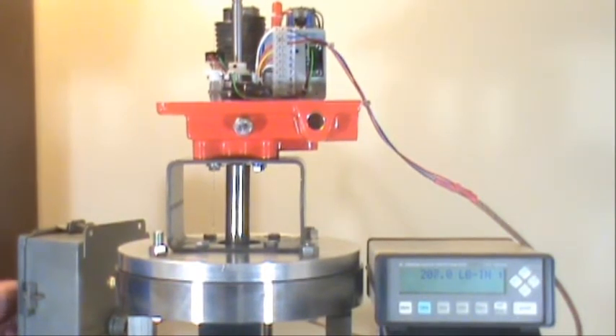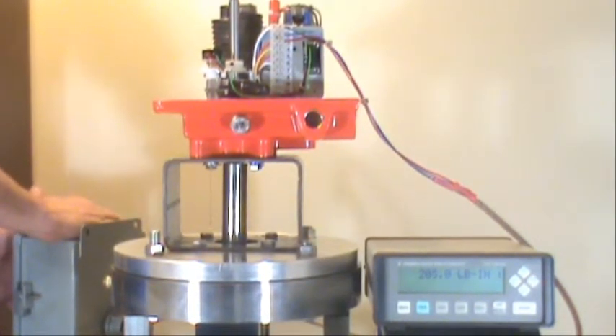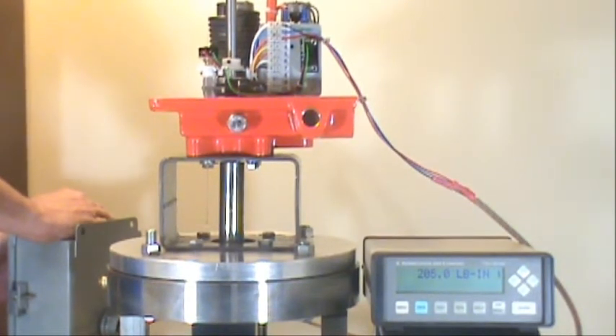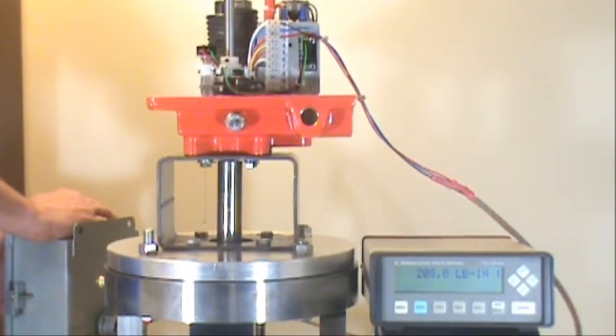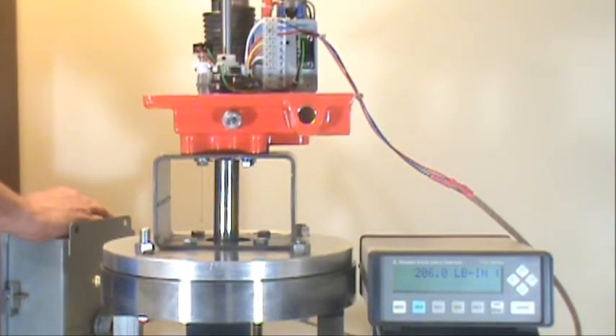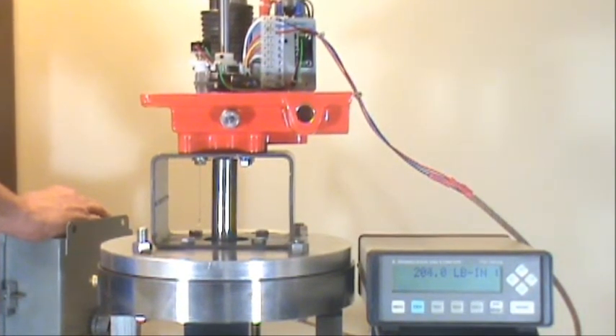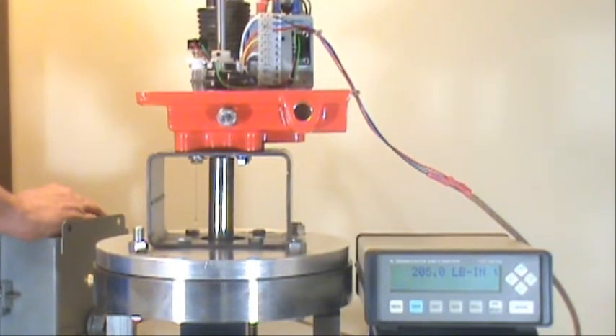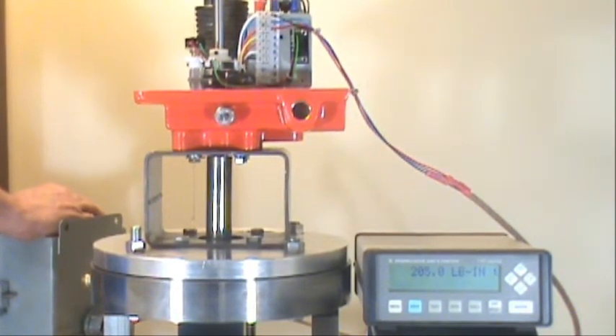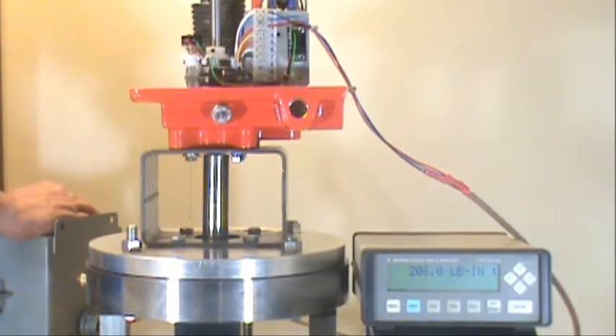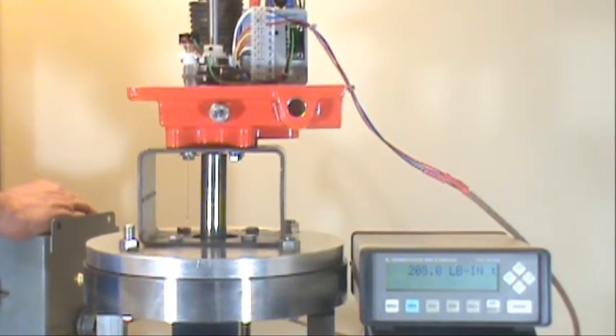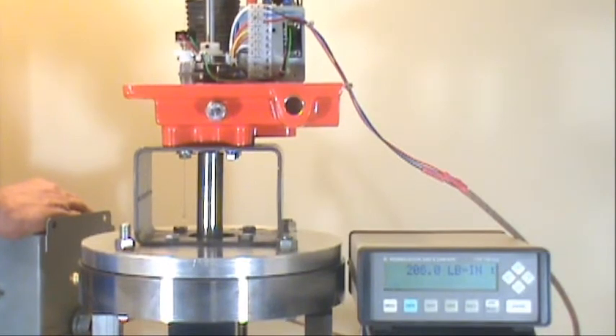That's a little bit over and above what the actuator's rated. But I do want to mention here that we always would like the customer to apply a safety factor for the valve. Because, as you know, if your valve's got 200 inch-pounds and our actuator is rated for 200 inch-pounds, there's a good chance that the actuator won't automate the valve.